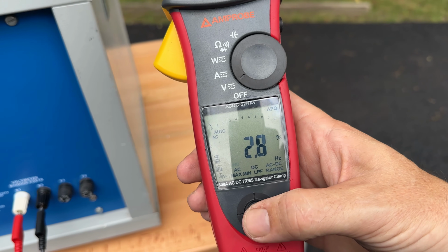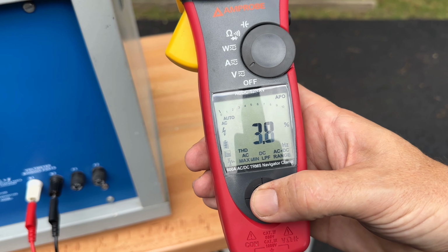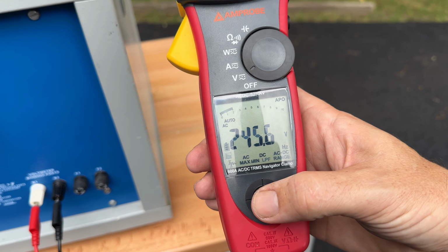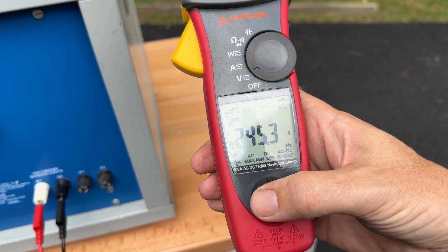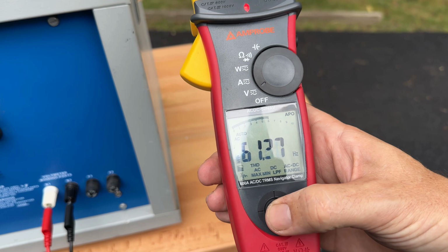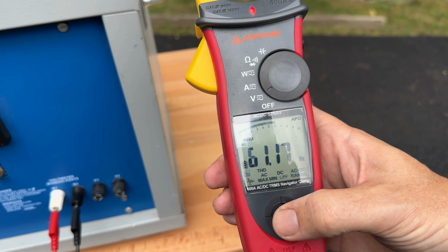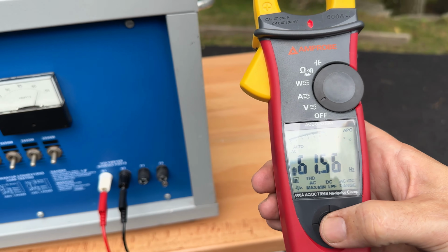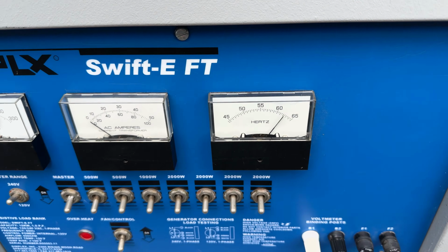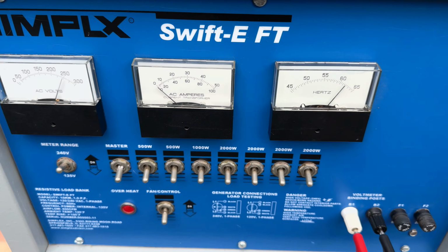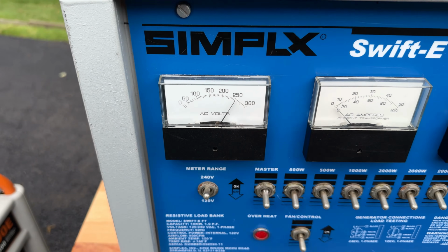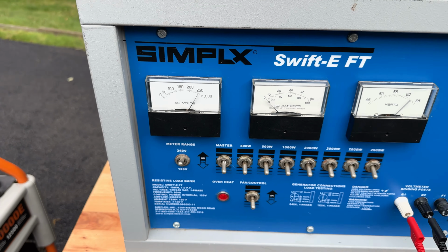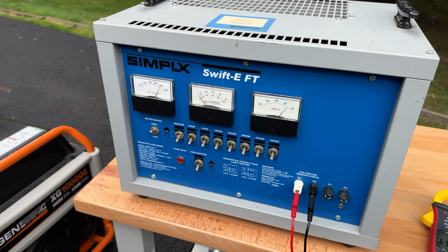So we're starting off at about 3% THD. Voltage is 245 volts, and let's take a look at the hertz. 61 hertz it looks like. Pretty close — the gauge here says 62 and 250 volts. Let's bring on the load and see how it does.